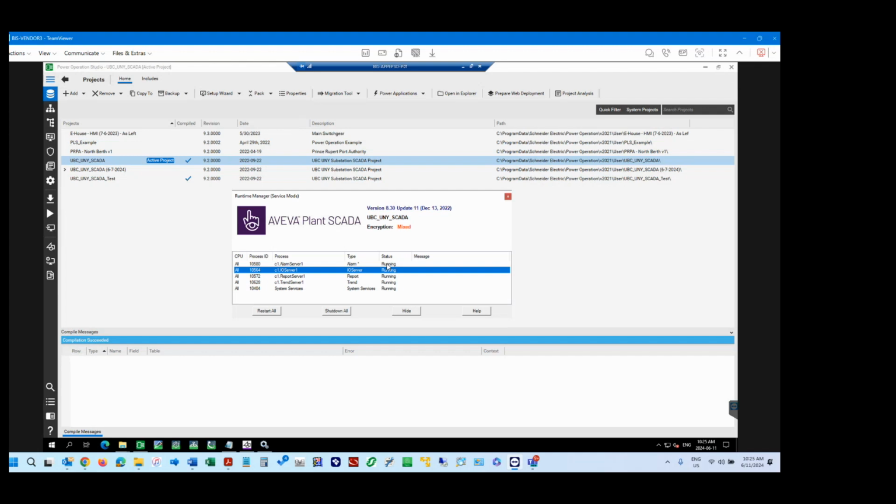Can ION Setup see it? Or you can just ping the IP of the individual meter. Since everything on the SEL side is beyond the RTAC, we can't ping each individual relay, unfortunately. So that would be up to the RTAC level to start to troubleshoot.